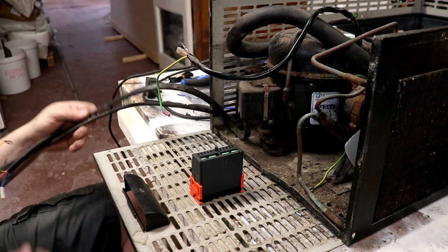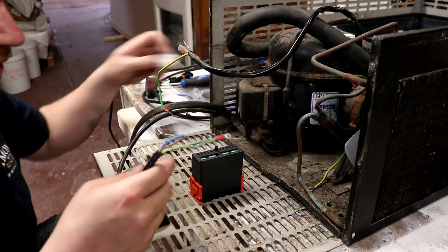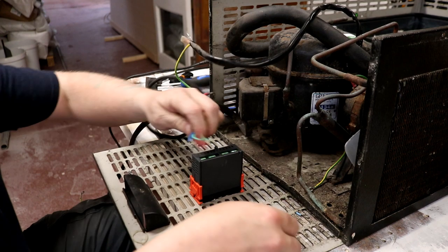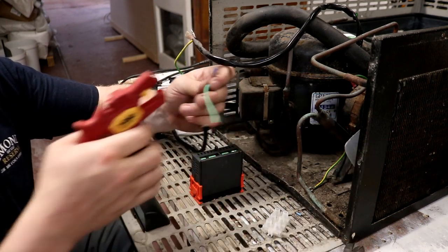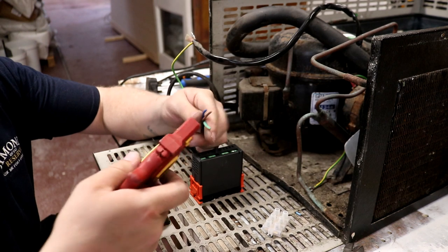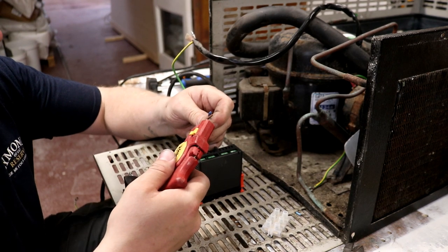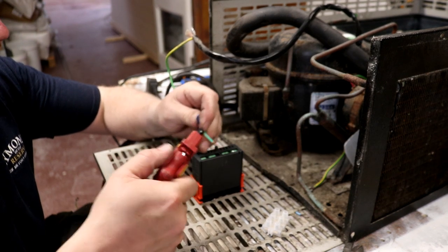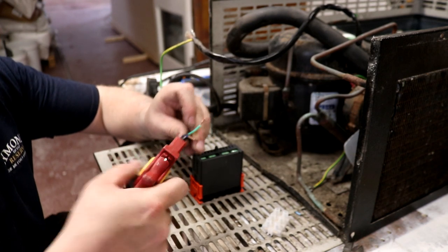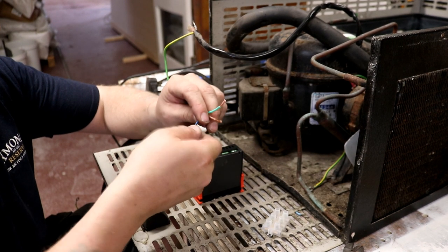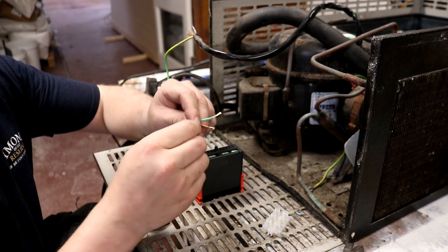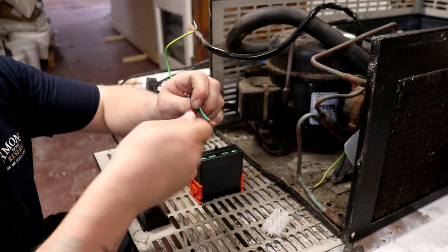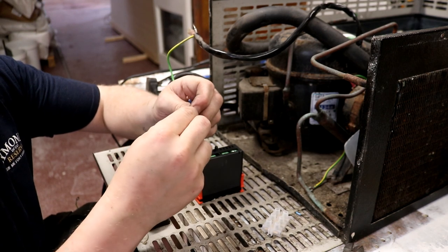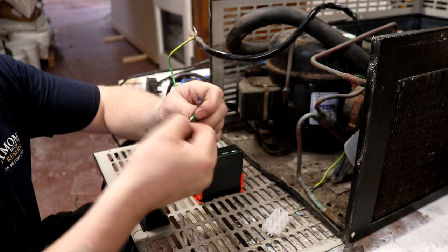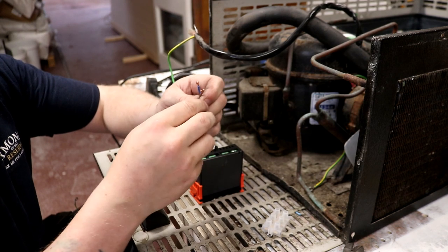First thing, we need to get all of our live and neutral cables onto some type of bus bar. So what we're going to do is strip all three of these cables back so we can utilize the existing plug. Then I like to twist the strands and fold them over to give us a nice big thick piece of copper for the grub screw in this terminal block to grab hold of.